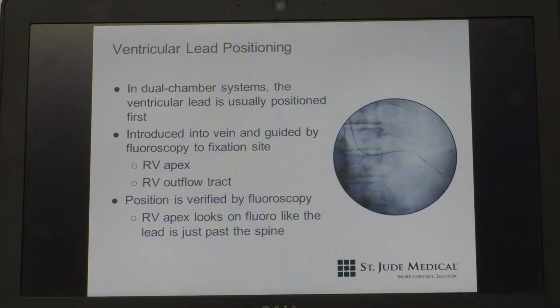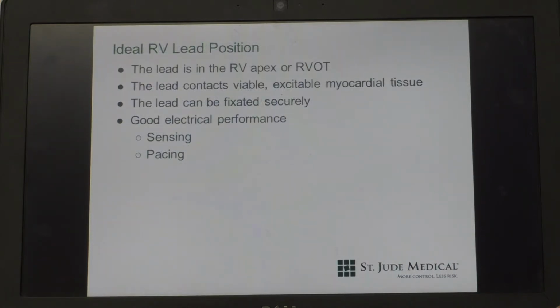So in dual chamber systems, the ventricular lead is placed first because this is the pacing lead, the most important lead. It's introduced into the vein and guided by X-ray to the RV apex or the RV outflow tract, and then you could just pull back. The position is verified by fluoro, and then we put the testing cables on, and the rep tests it to make sure it's a good placement. We test sensing and threshold. A threshold is the minimum amount of energy required to make the heart pump. So we just lower the voltage until we lose capture. You can tell by the morphology of the QRS, and the threshold is the lowest voltage that made it capture.